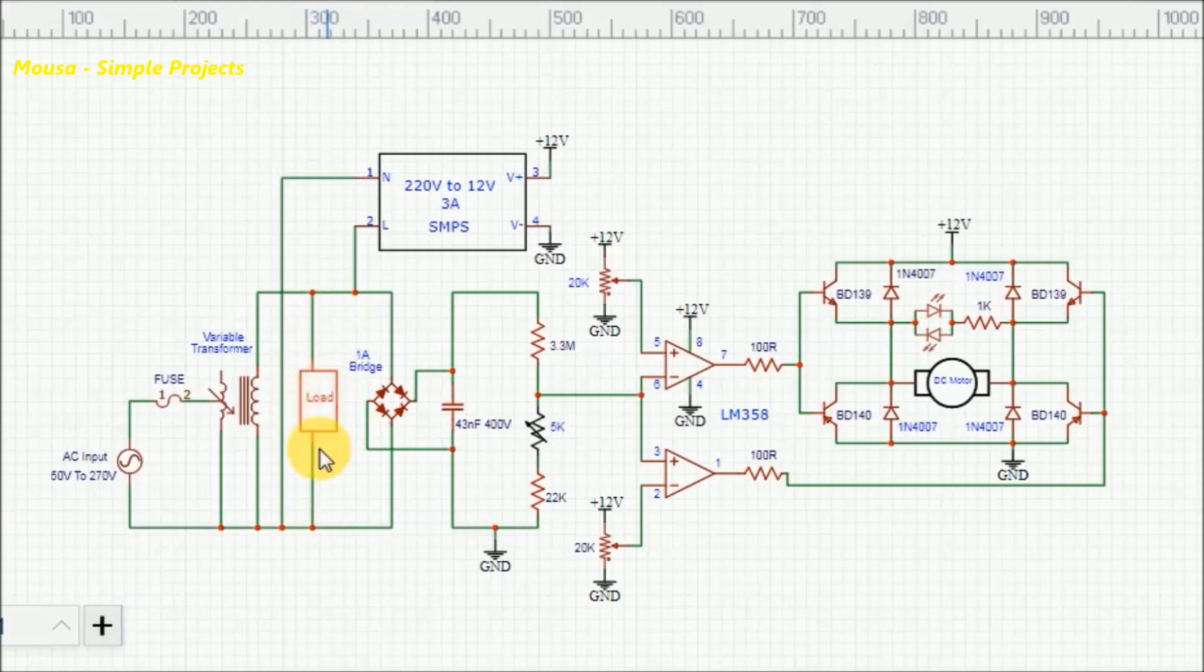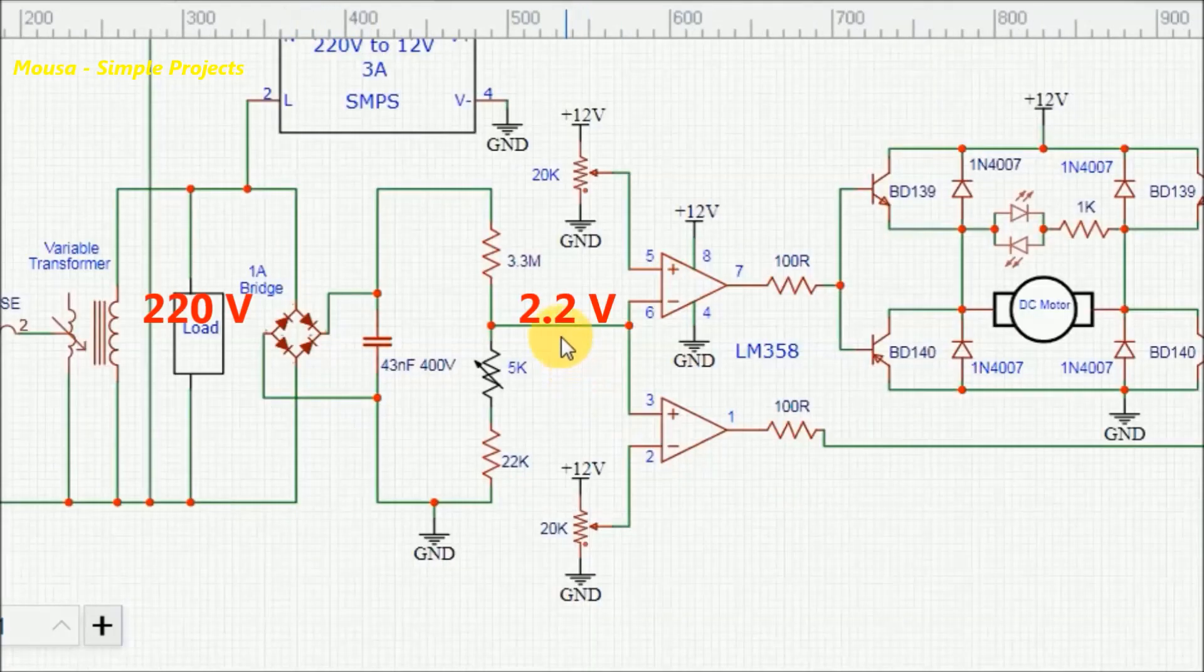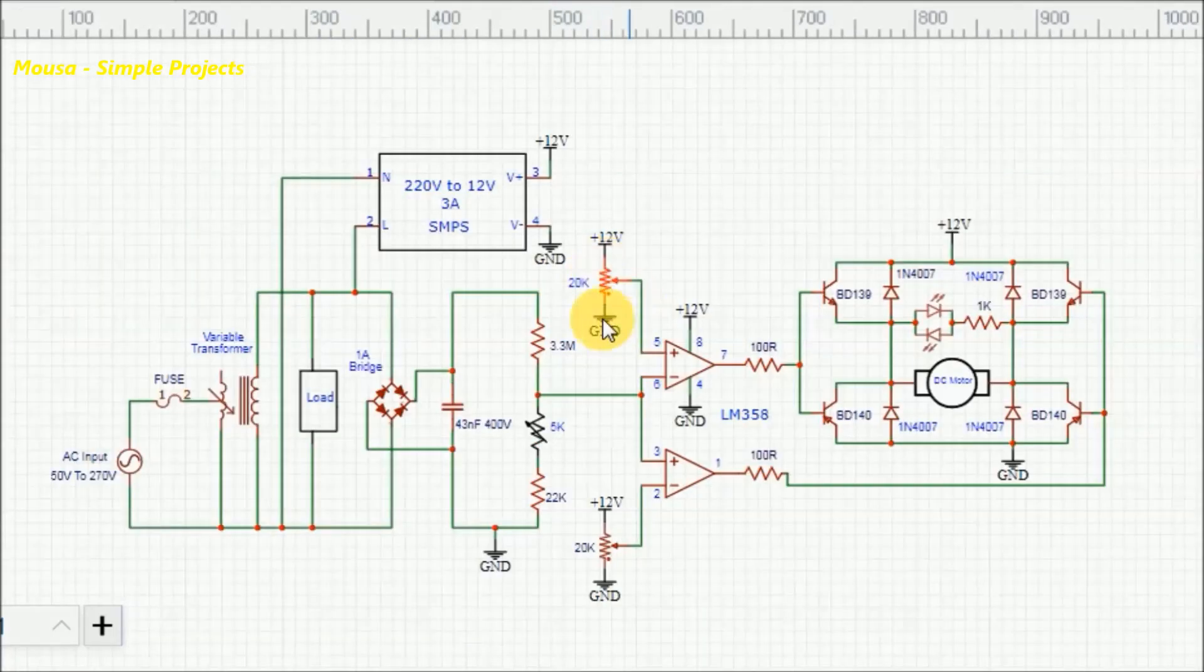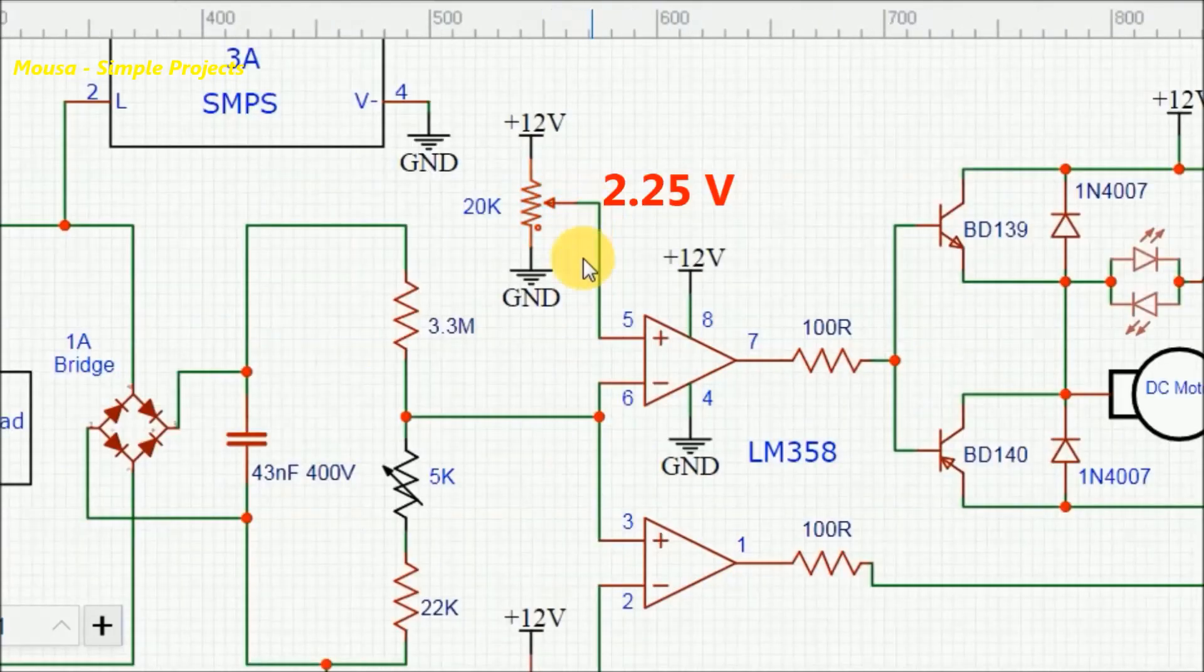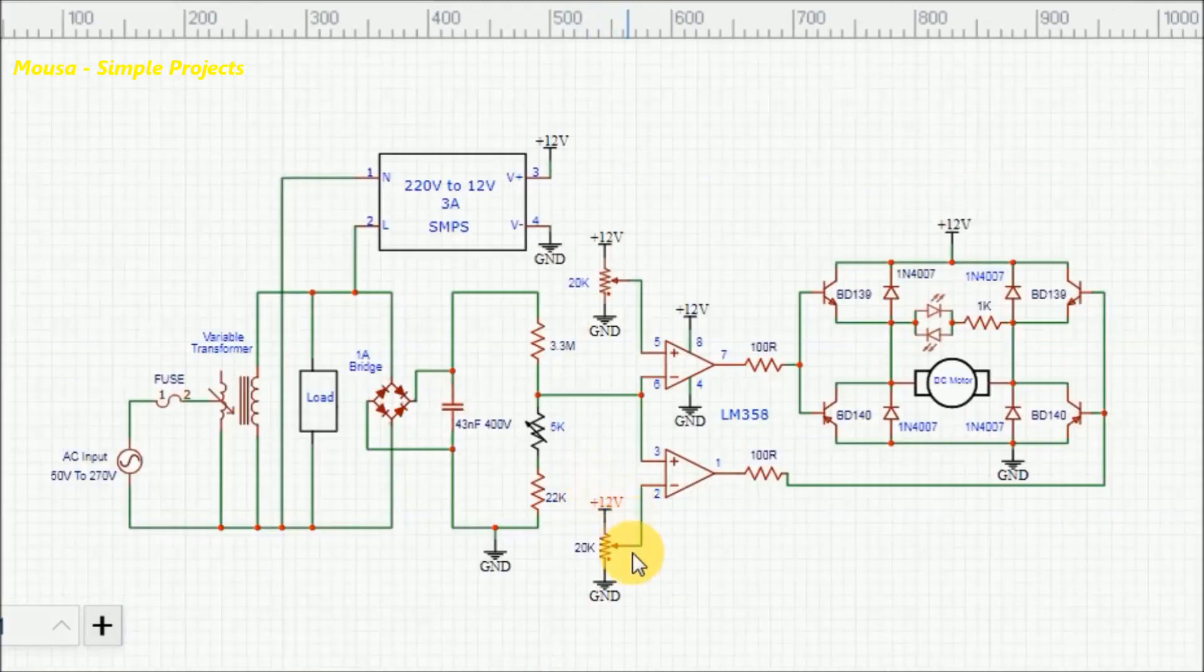For example, let's say the voltage at the secondary side of the transformer is 220 volts. So the voltage at this point should be 2.2 volts. Then you have to set the next potentiometer until the voltage at this point becomes equal to 2.25 volts. And finally, set the last potentiometer until the voltage at this point becomes equal to 2.15 volts.